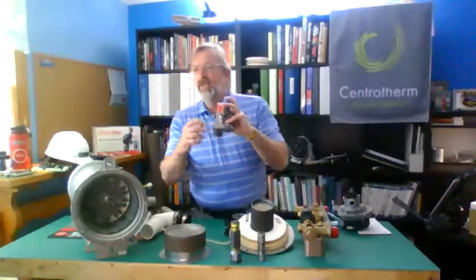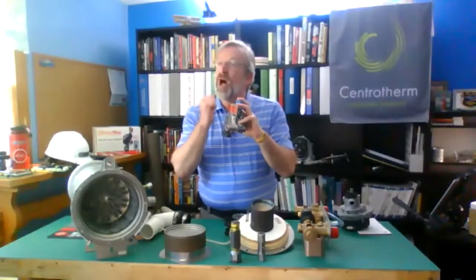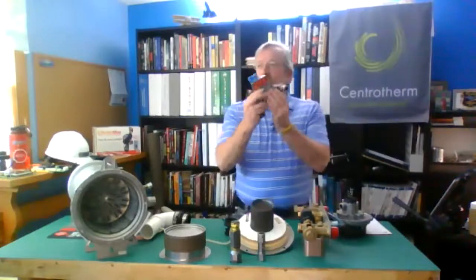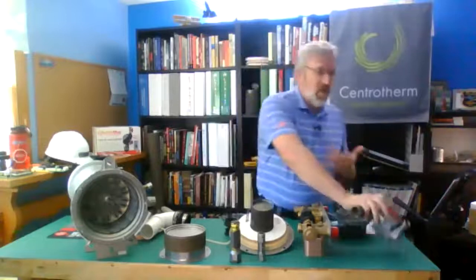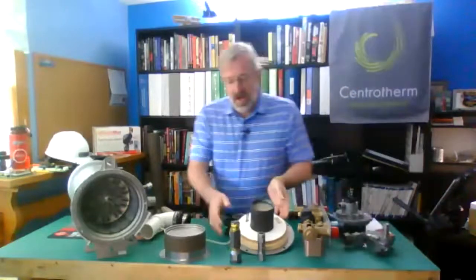Now, I see you there, Carl. You look like you're a pretty good sized guy. So I'm going to recommend a small adjustable wrench. We don't need to crank on it. It's just a little bit. It's under negative pressure with a gasket. So we tighten it and then we give it that little bit. So we untighten it the same way. Now, once I do that, this guy's going to pivot away.